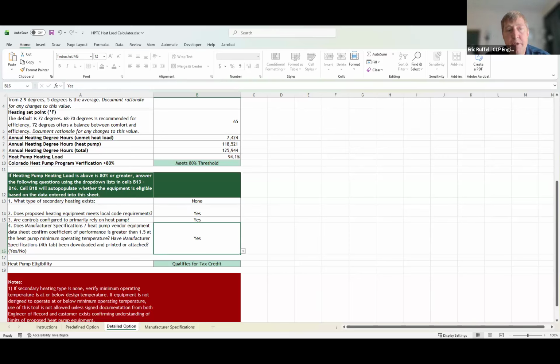In reviewing recent grant applications across Colorado, engineers have commonly been designing supplemental heat for the coldest days. A heat pump works by extracting thermal energy from the outside air. On very cold days, there's less thermal energy available outdoors, or it's less dense, so the heat pump has to work harder. As recent as 20 or so years ago, heat pumps really struggled to operate below freezing. But the cold climate heat pumps in particular are doing much better. The technology is much better, and now there are cut sheets showing operational temperatures below 0 degrees Fahrenheit.